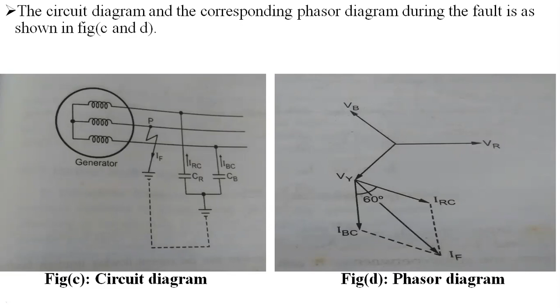then the fault current over here is the resultant of this IRC and IBC. Since the incoming current must be equal to the outgoing current, or by Kirchhoff's law, the summation of all currents must be equal to 0. Thereby, the fault current is the summation of our IBC and IRC, which have a phase difference of 60 degrees between them.